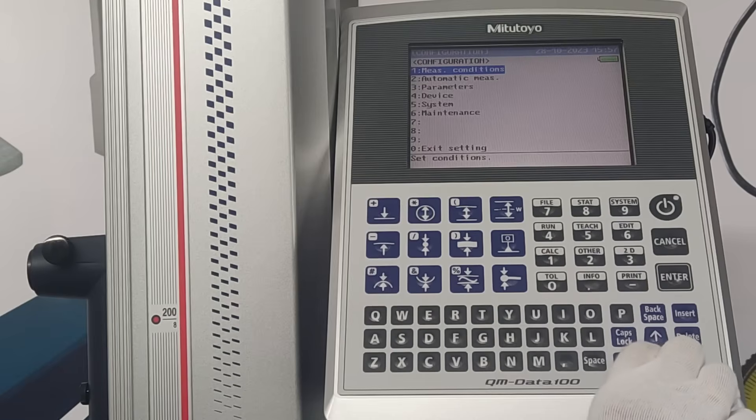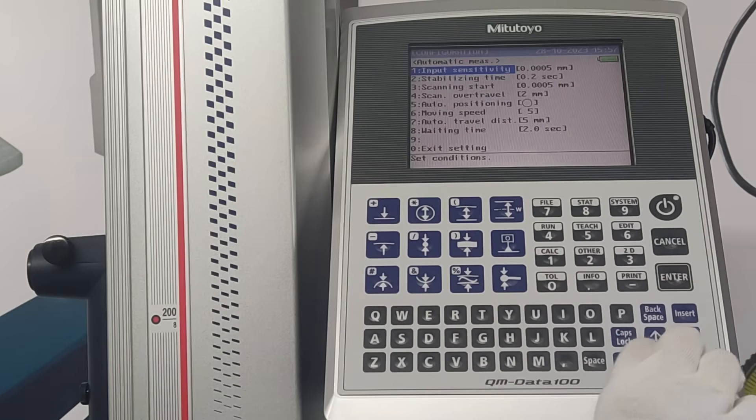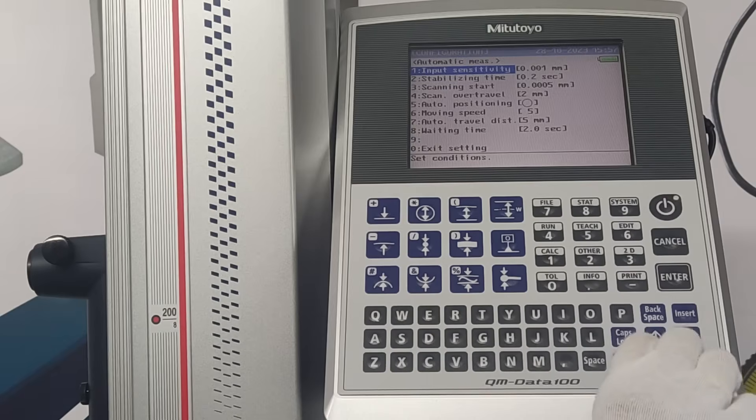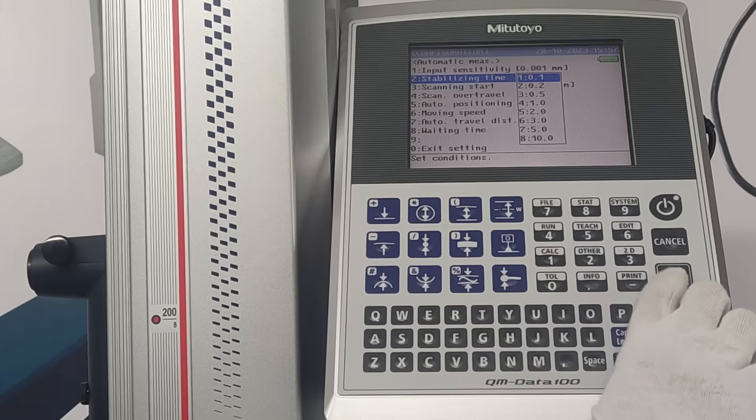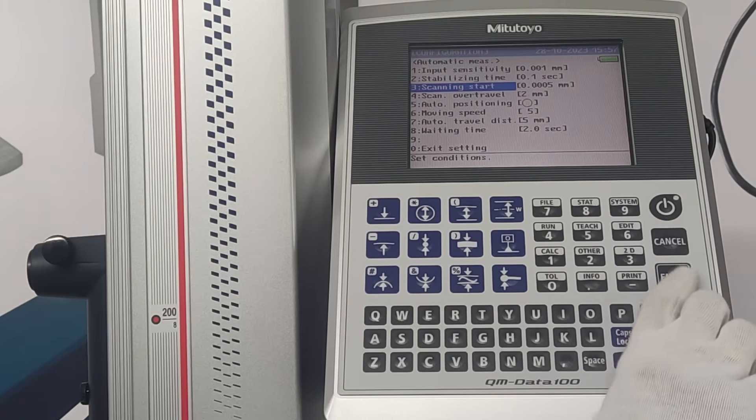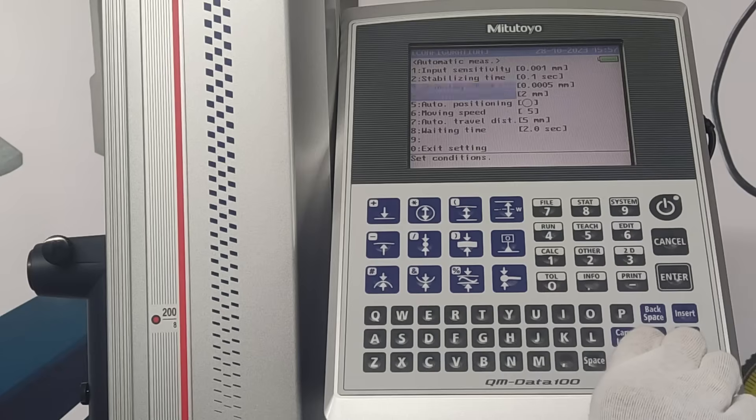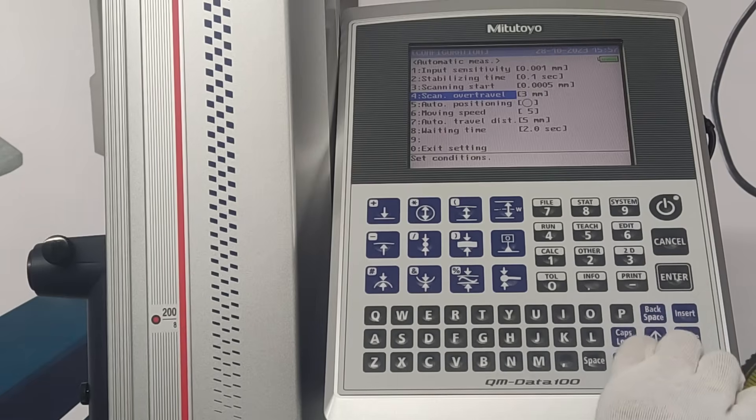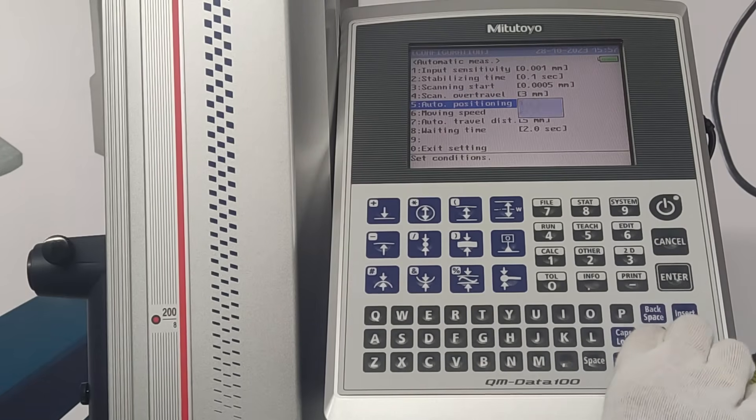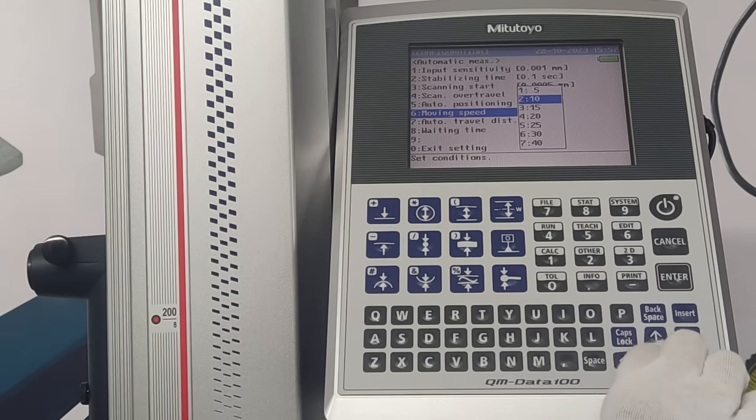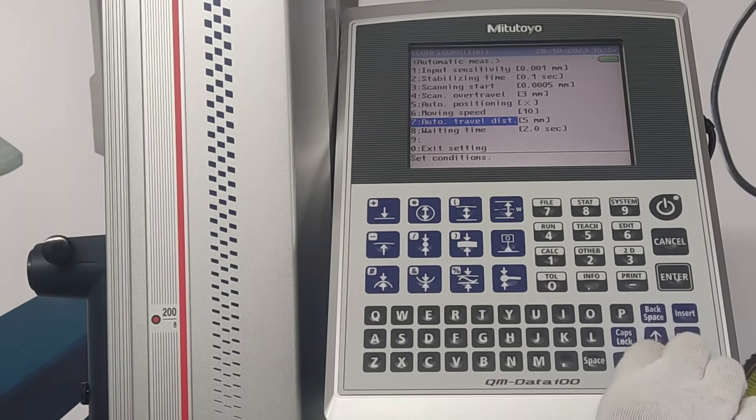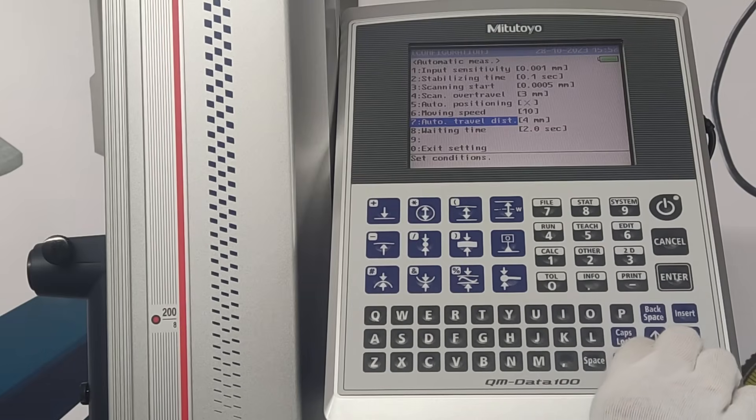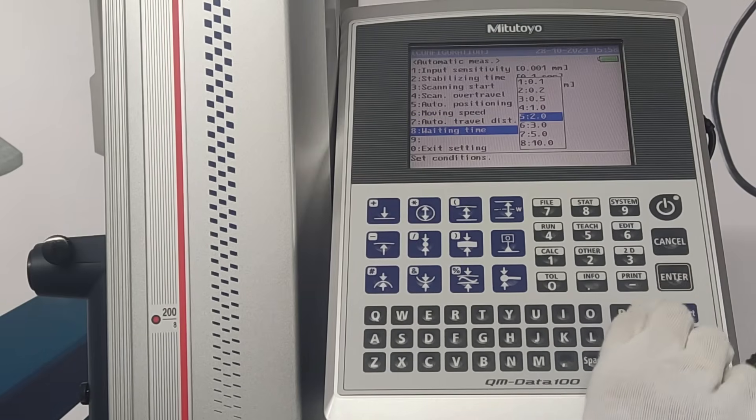Under automatic measurement, input sensitivity is defined in mm. Stabilizing time in seconds. Scanning start in mm. Scan over travel in mm. Auto positioning can be turned on or off. Moving speed is defined. Auto travel distance can be defined in mm.